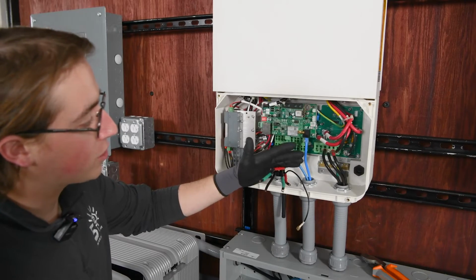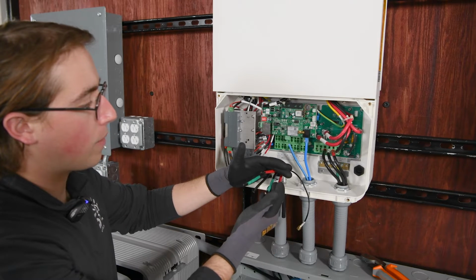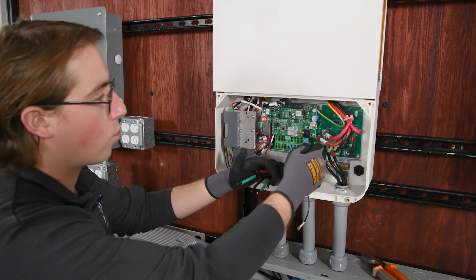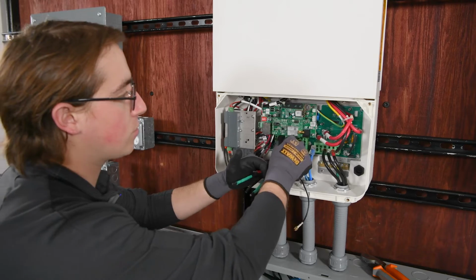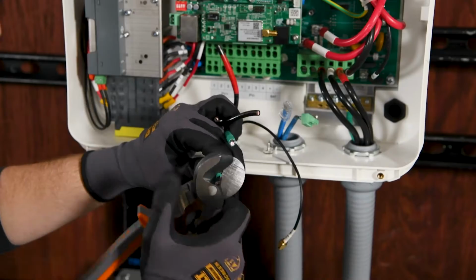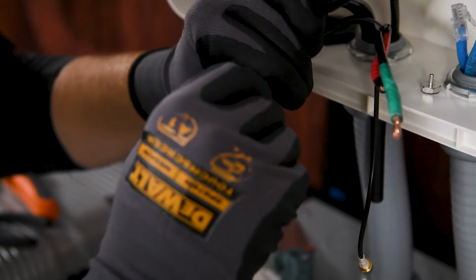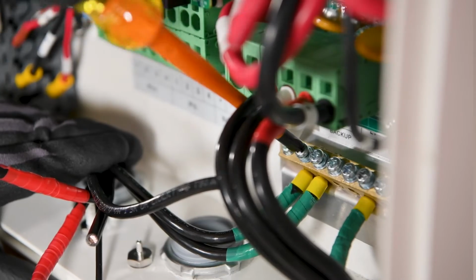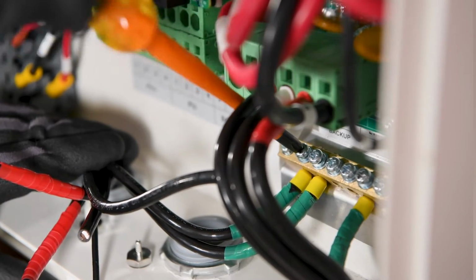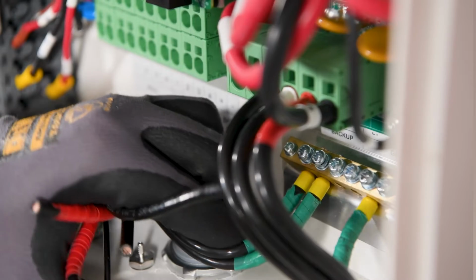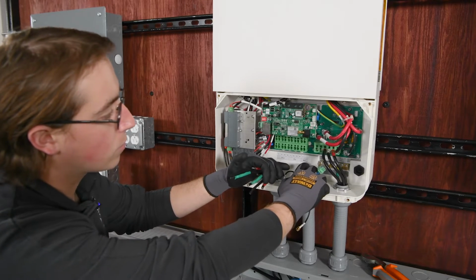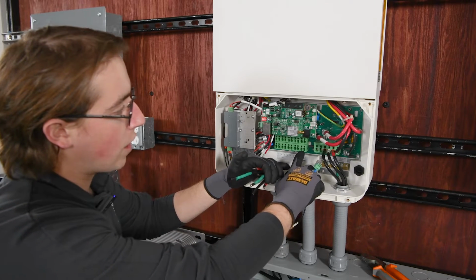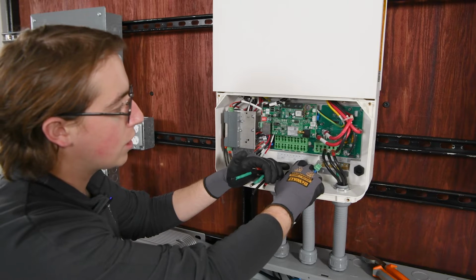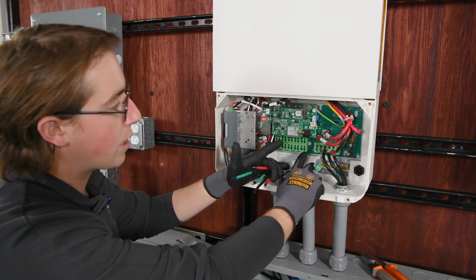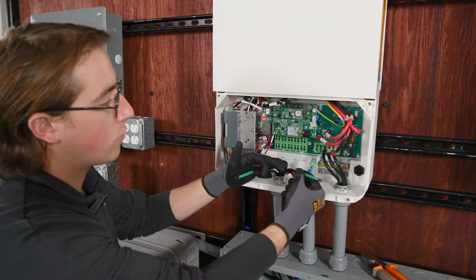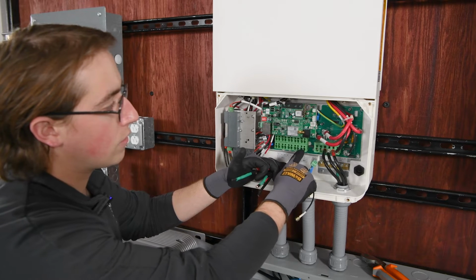With our communication setup now, we will go ahead and wire up our battery wires here. So I'm just going to go ahead and move these communication cables out of the way. We'll strip and ferrule each of our battery conductors and get them connected to our battery positive and negative terminals. Something to mention with the 11.4 and other Growatt systems is that we have 2 terminal blocks for our batteries, so we don't have to go to any kind of combiner box. We can take each output from our battery and go directly to the inverter.